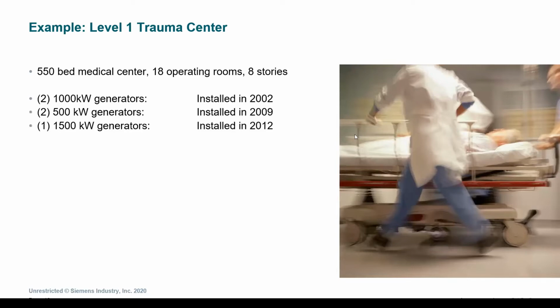So we're going to look at applying this in an actual specific example. The example we're going to examine is a level 1 trauma center. And for the example, 550 bed medical center, 18 operating rooms, and 8 stories. A facility like this, we'd expect multiple generators and a couple different transfer switches for each of the branches. In this example, we have 5 generators of different sizes and installed in different years.